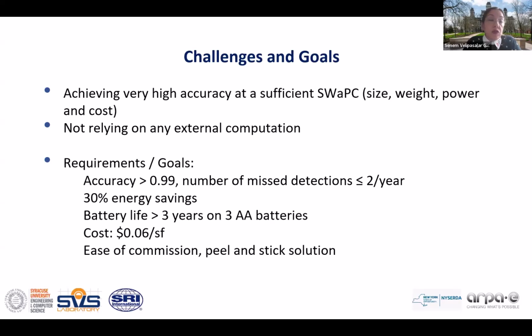The goal in terms of accuracy was to achieve greater than 99% accuracy with less than 2 missed detections per year. By doing so, we wanted to save 30% in energy savings, provided from utility bills. Another goal was a battery life greater than 3 years on 3 AA batteries. The cost requirement was 6 cents per square foot, and another goal was to have something almost peel and stick, to provide ease of commissioning.